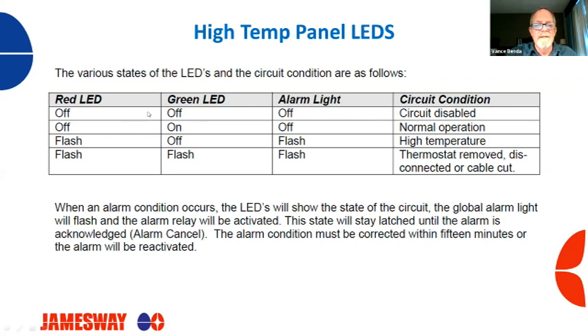If something happens inside your incubator that causes the temperature to go above your set point, the red light on the individual circuit is going to flash, and that global alarm light down in the bottom left of the control panel is going to flash. And then if you have this situation, we've got a problem out of your thermostat. It's either disconnected or your cables have been cut or something.